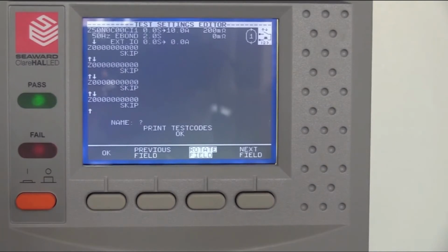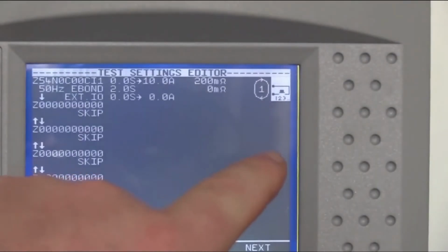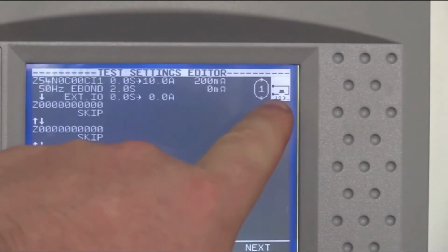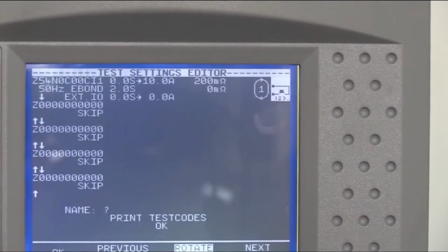Now this can be particularly useful when you're sequencing tests that are within a test enclosure. So we may want to press the green button for the very first test and then allow the test to automatically continue, providing all of the tests are passing. So what we're going to do is exactly that kind of scenario. I'm very quickly just going to change the icon to our start condition. So you'll notice the small little button icon. That indicates that the test will start on press of the green button.